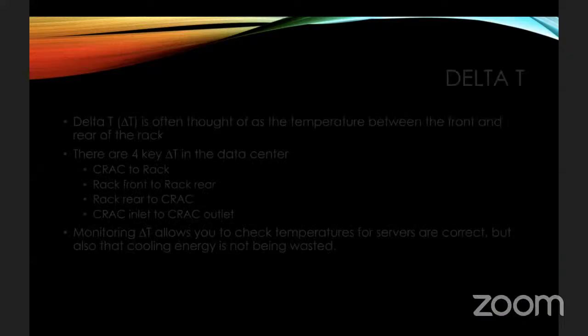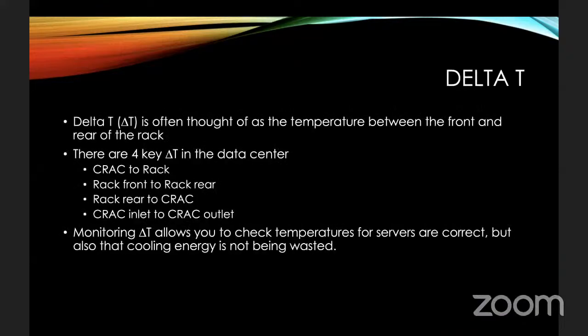The next metric that is important for us to consider is the delta T. Although not directly related to energy consumption and water consumption, it is a byproduct of those. Now, most people, when they consider the delta T of a data center, are thinking about the delta T across a rack. That is the temperature difference between the air entering the rack and exiting the rack. But there are, in fact, 4 key delta Ts in the data center that you should consider.